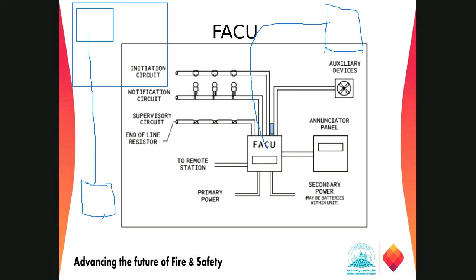This is just annunciation. So there is no control at all in the annunciator panel. They are only monitoring the alarms and the condition of the main panel. They are just monitoring the condition, and will go to the main panel to check. On the annunciator panel, there will be just the LCD screen and some signals, like green, yellow, and all kinds of lighting. So it will show what is happening. So it is just for when it is far away from the main control unit.